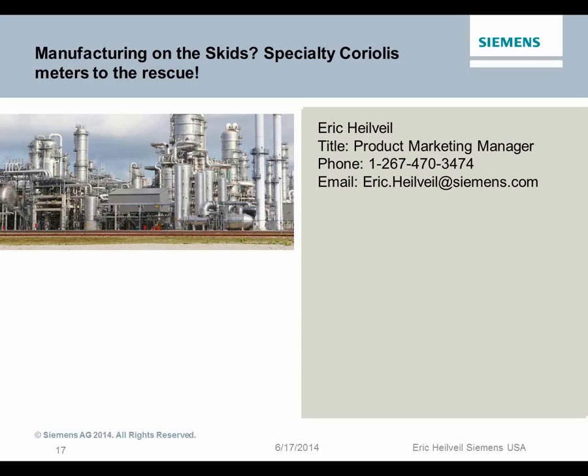Our tubes are very, very small, short in length, in other words. They offer very gentle bends, providing very low pressure drops. So the reason I can't give any absolute answers is the pluses and minuses are usually very application dependent. I can't say Siemens Coriolis always offers lower pressure drop, but oftentimes we do. But a lot of that depends on the fluid. As far as accuracy goes, essentially the same.